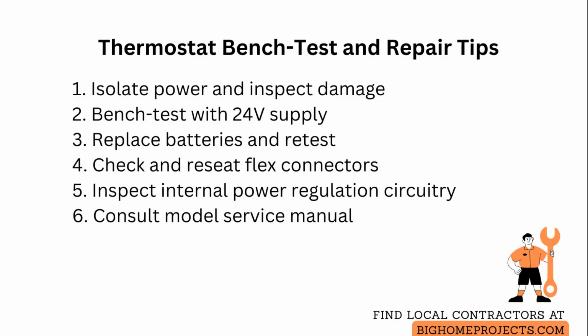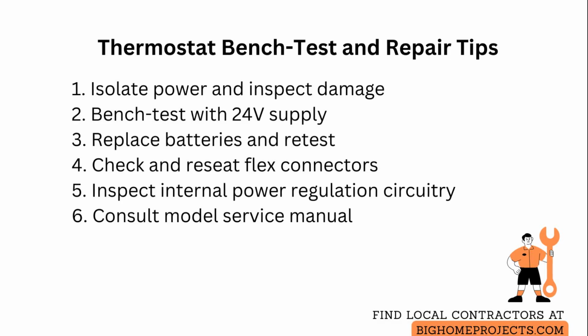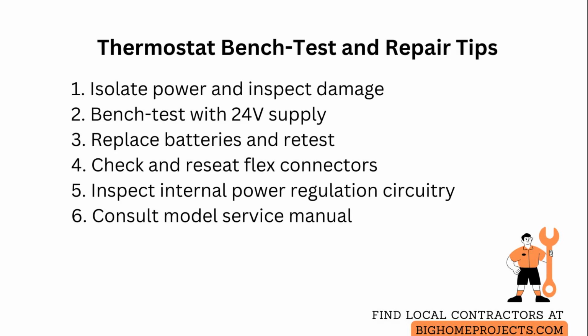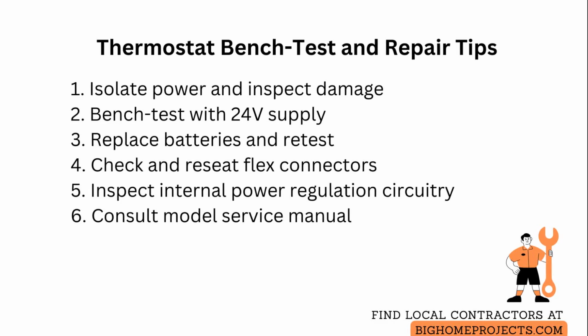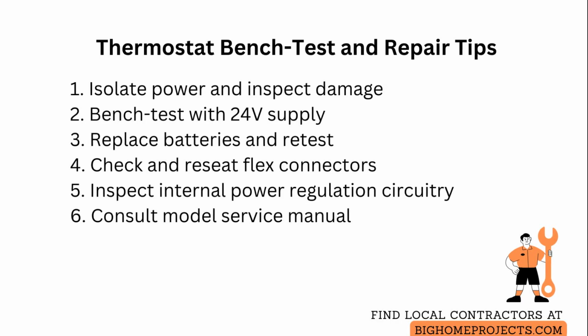corrosion, or loose connectors. Remove the thermostat from its base to check harness pins for bent or oxidized contacts. Test the device at the manufacturer-recommended bench setup if available by applying a stable 24-volt alternating current supply to the appropriate power terminals and verifying whether the display and input functions initialize.